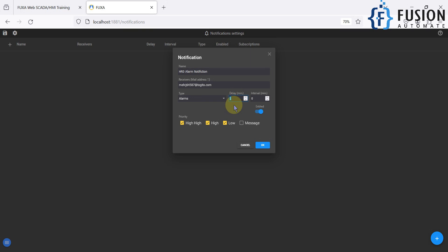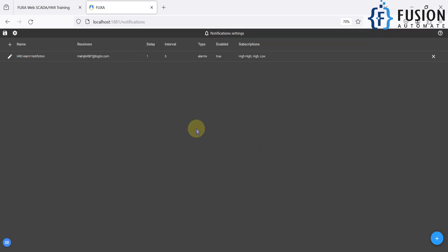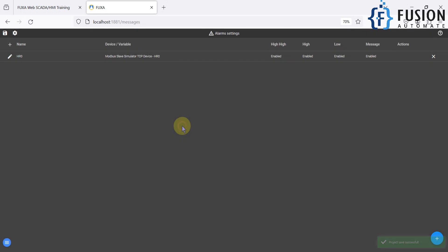For delay, we will wait one minute before sending the email. For interval — if the alarm condition stays active, this specifies how often to resend the email. If you keep it at one minute, and the alarm stays for 30 minutes, you will get a mail every minute. If you set five minutes, you get a mail every five minutes. Press OK to add the notification, then save the project.